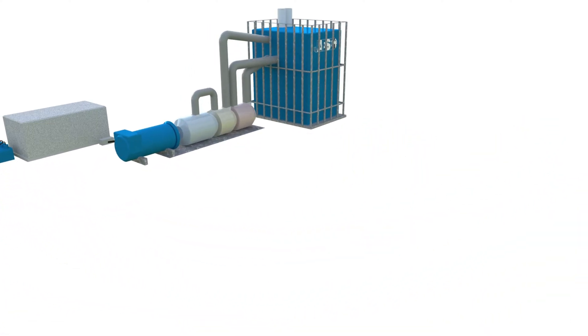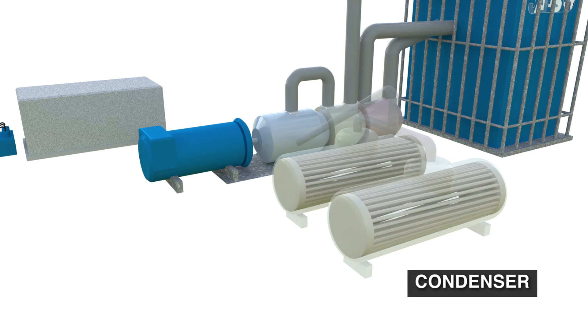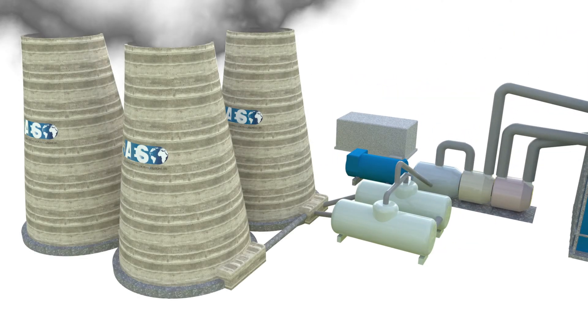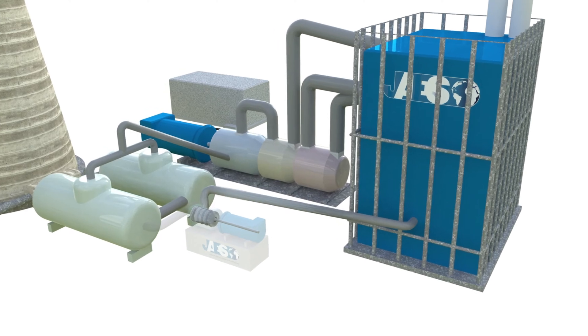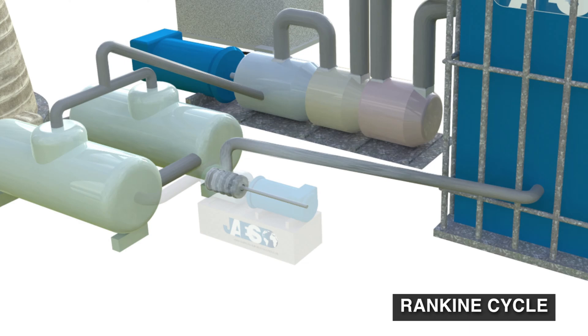The turbine's waste steam is sent to a condenser, where its temperature gets decreased by a water flow coming from a lake, a river, or — as in this example — the atmosphere itself, by using the characteristic cooling towers. In this way, the steam returns to its liquid state. Then a hydraulic pump increases the pressure of the water so that it can be sent to the boiler again. This process is called the Rankine cycle and can be repeated to provide constant electricity production.